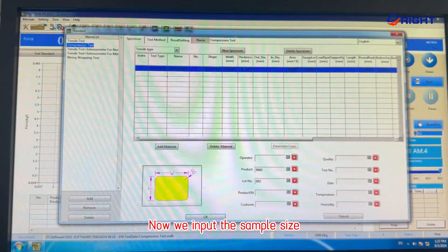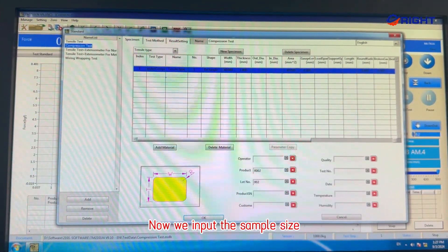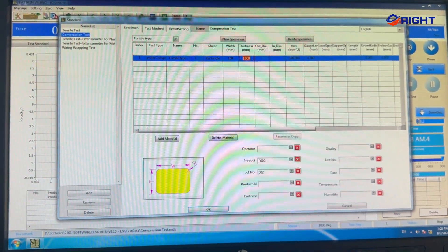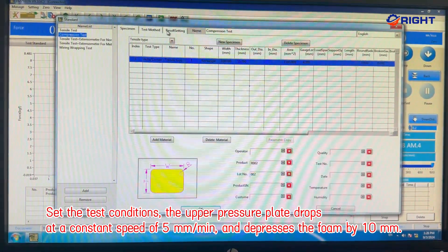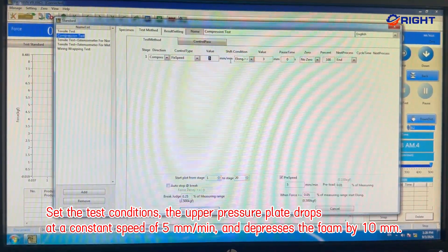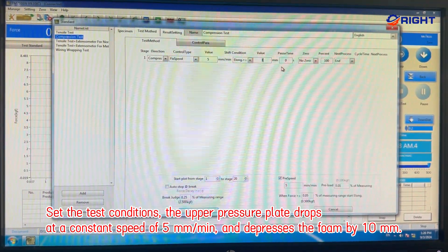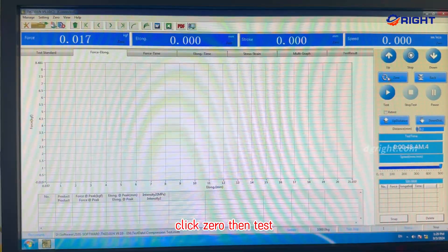Now we input the sample size and set the test conditions. The upper pressure plate drops at a constant speed of 5 mm/minute and depresses the foam by 10 mm. Click zero, then test.